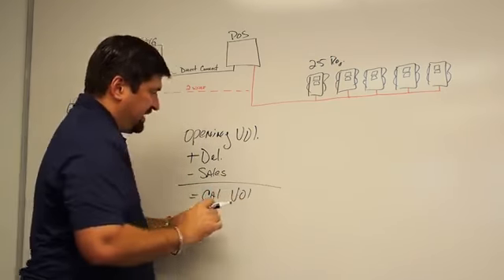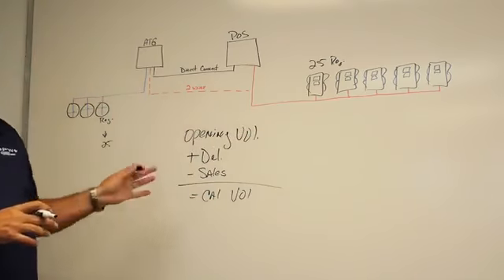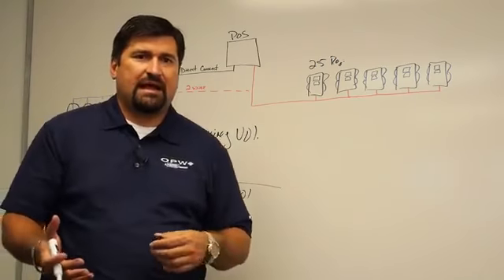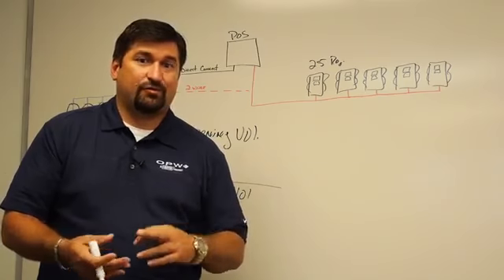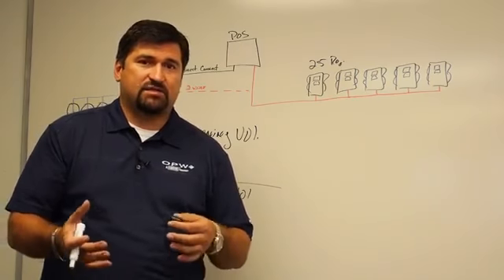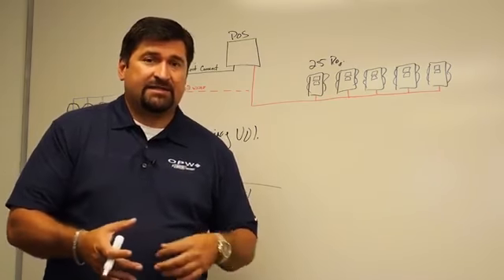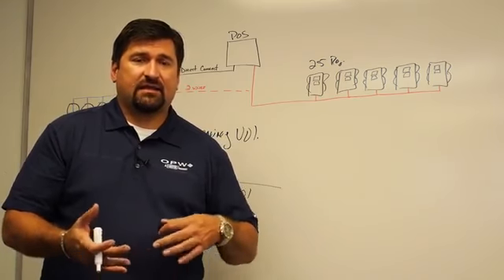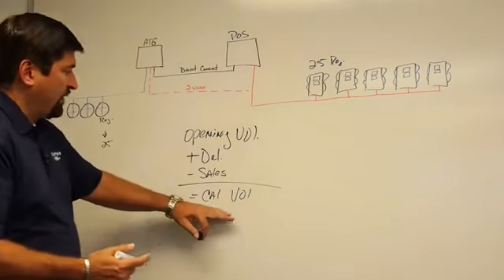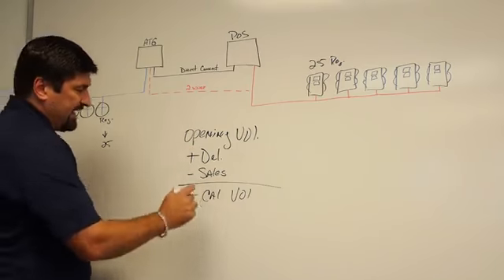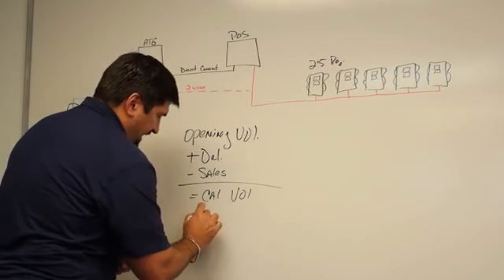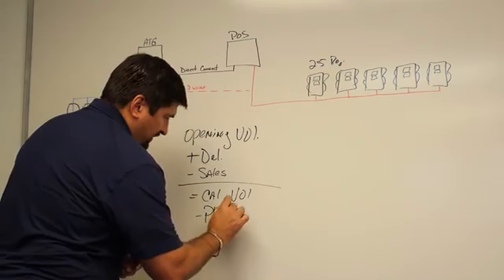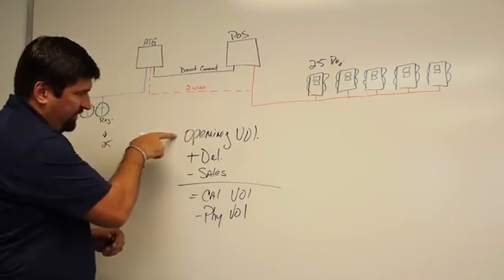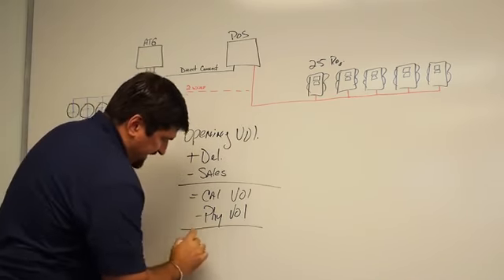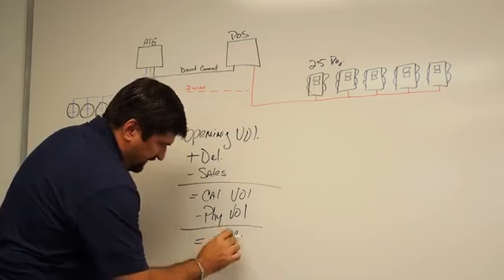calculated volume. Now this is going to go on, and I'm using 25 gallons, but in a typical station you may have 1,500, 2,000, 3,000, even 4,000 gallons dispensed every day. It just depends on the size of the station and the activity that you have. When I look at calculated volume, the next day I take calculated volume minus physical volume, which is my opening volume of the next day, and that will equal my daily variance.